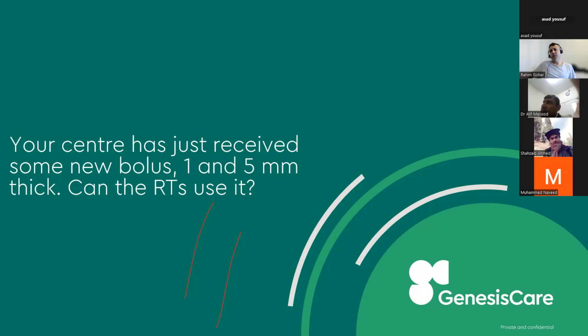We place the chamber, take the reading, and then place the bolus and take the reading again. Ideally the reading should be the same, but if there is a difference, it will reflect how its density is different.